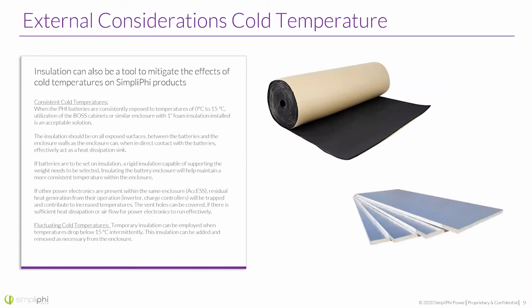This is a go-to of mine. I mean, it's the most simple method when looking at how do we mitigate cold temperatures? Insulation is the easiest. And we have some suggestions for insulation that we would recommend specific for batteries, making sure you're not ending up with an insulation that could be dangerous, that gets warm and maybe heats up and catches fire. I've seen people use some pretty bad insulation that's not approved. So I would always reach out to us first for recommendations.